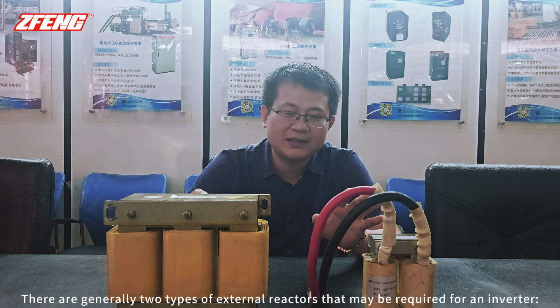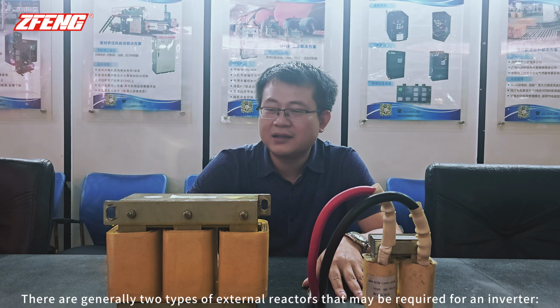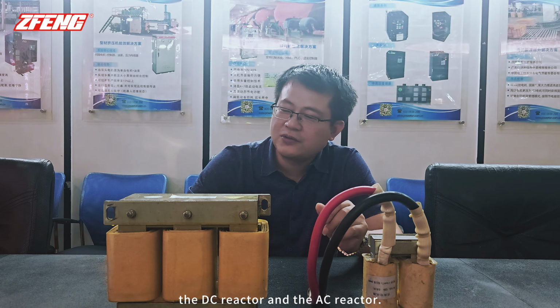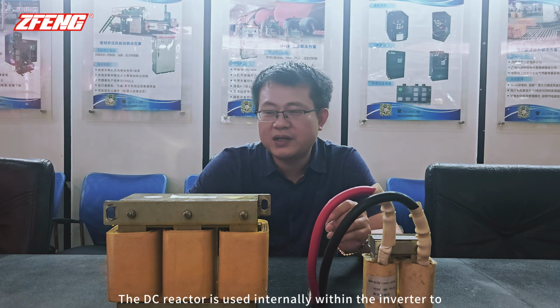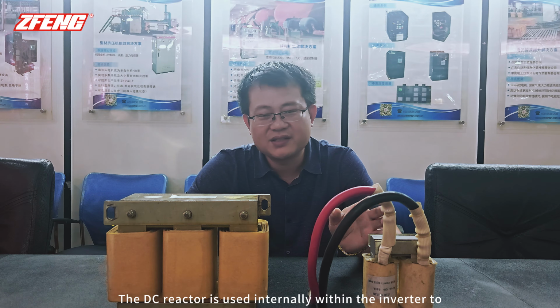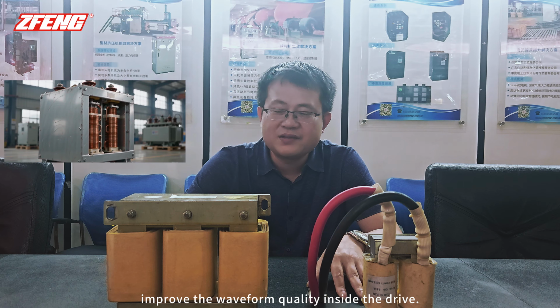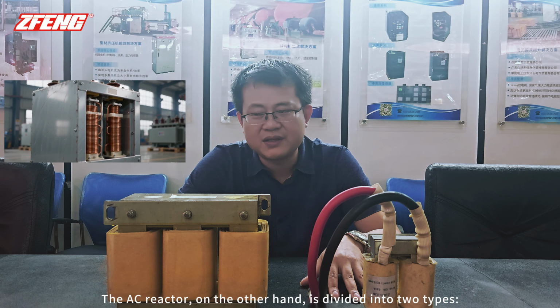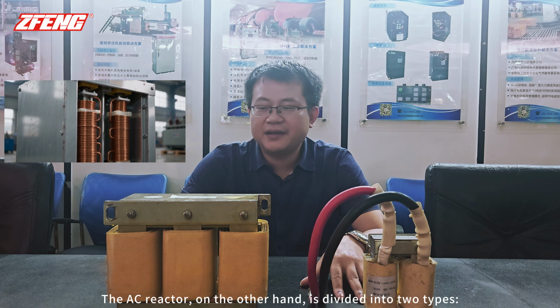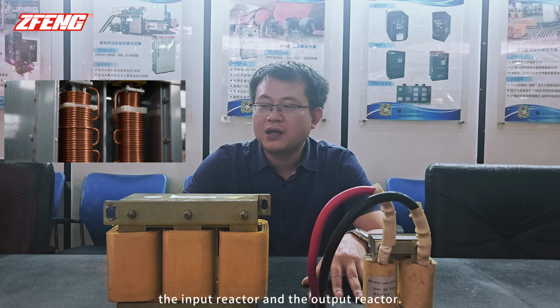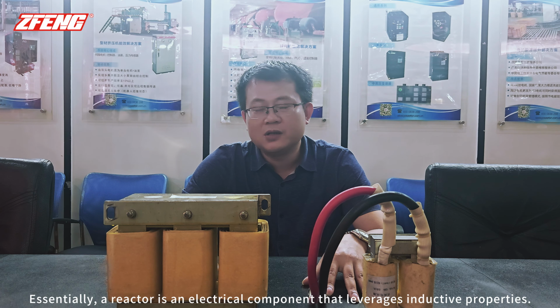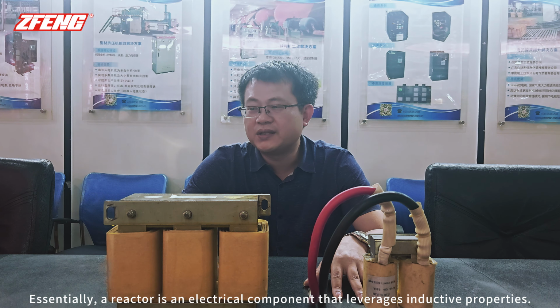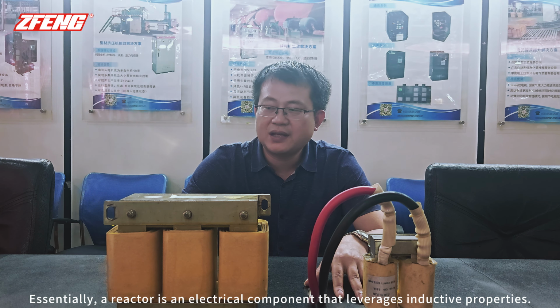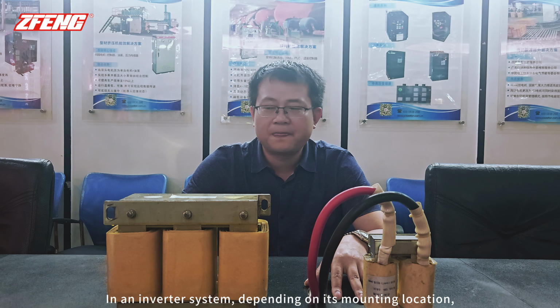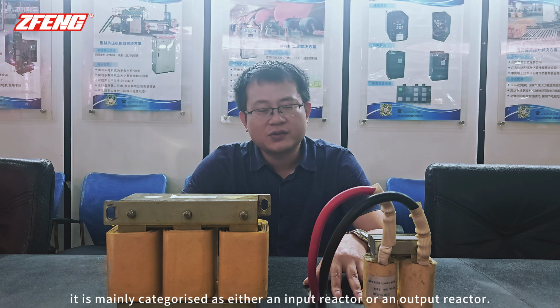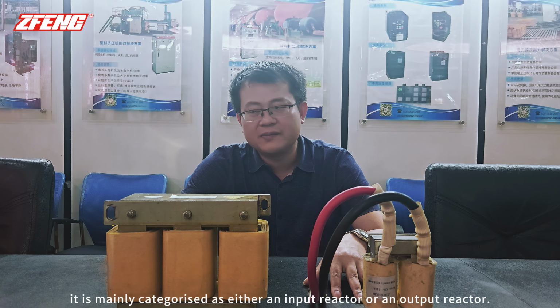There are generally two types of external reactors that may be required for an inverter: the DC reactor and the AC reactor. The DC reactor is used internally within the inverter to improve the waveform quality inside the drive. The AC reactor, on the other hand, is divided into two types: the input reactor and the output reactor. Essentially, a reactor is an electrical component that leverages inductive properties in an inverter system. Depending on its mounting location, it is mainly categorized as either an input reactor or an output reactor.